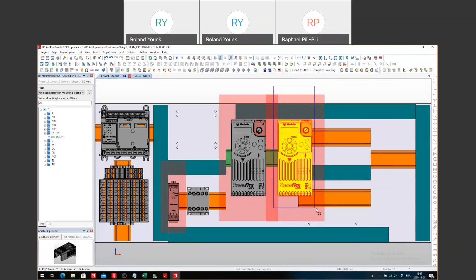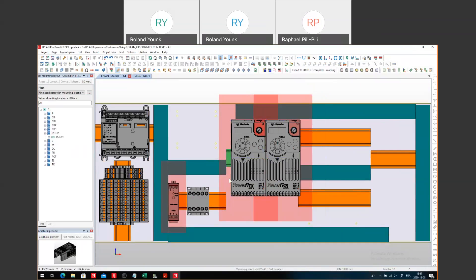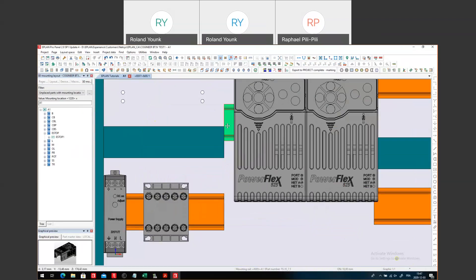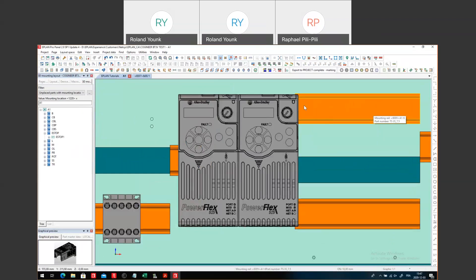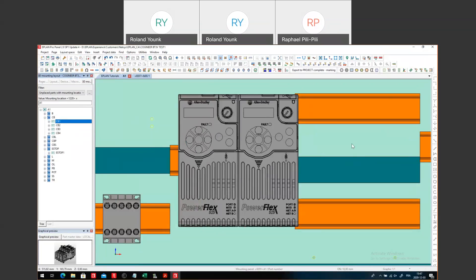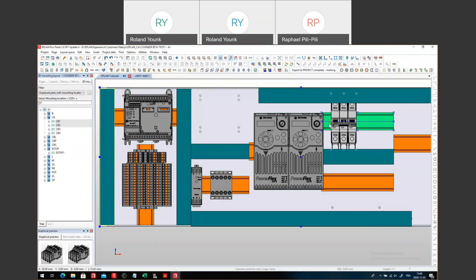Looking through the individual documents I found on the PowerFlex, I actually saw that we are allowed to have them sitting next to each other, so that is possible. The other thing I want to do is go back and move this whole thing a little bit down — in EPLAN I can just move and align it with this here, and that makes it just perfect. I'll have to readjust for the next component, so maybe some circuit breakers CB1, CB2, CB3, which I want to place at the top. Some of these devices are fairly big, some smaller — I can try and drop them, but I have to be careful not to go to the edge.